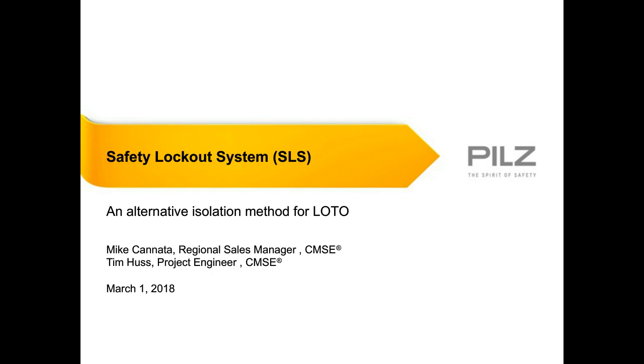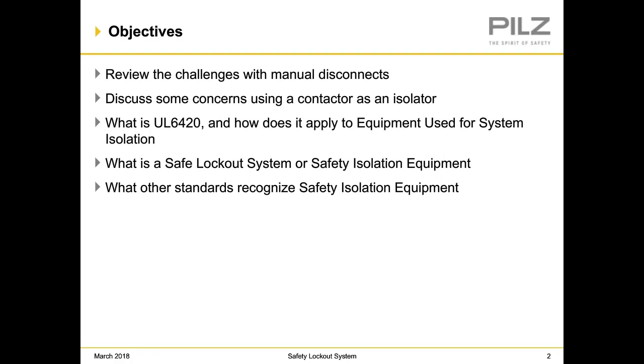But we'll get into it here and talk about the safe lockout system and an alternative isolation method for lockout tagout. Some of our objectives today are to review the challenges with manual disconnects, discuss some of the concerns using a contactor as an isolator, discuss UL6420 and how it applies to equipment used for system isolation, talk about what is a safe lockout system or safety isolation equipment, and then discuss some of the other standards that recognize safety isolation equipment.